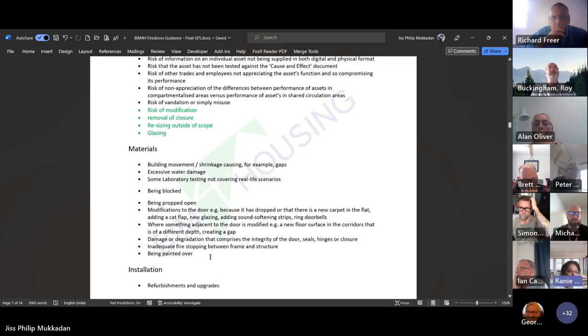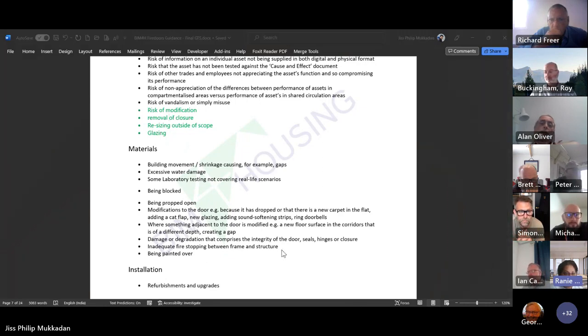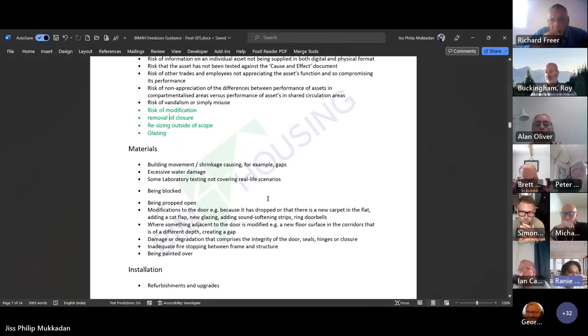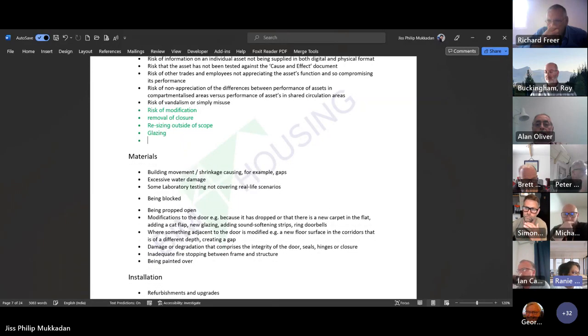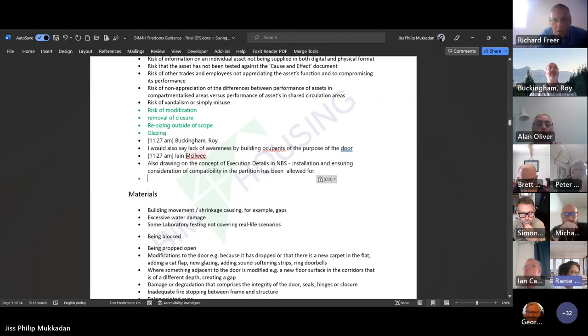It might be, say, in a mental health institute where you have high security, but you have say 60-minute fire doors as well. And in instances where the cause and effect isn't programmed properly, or isn't maintained properly, the electric locks might fix into position where the door should be opened on activation of the fire alarm. Sometimes it's fixed into position and therefore causes an entrapment situation. So in terms of the fire door being connected to other electrical or mechanical devices, I think we just need to be a little bit aware of that.